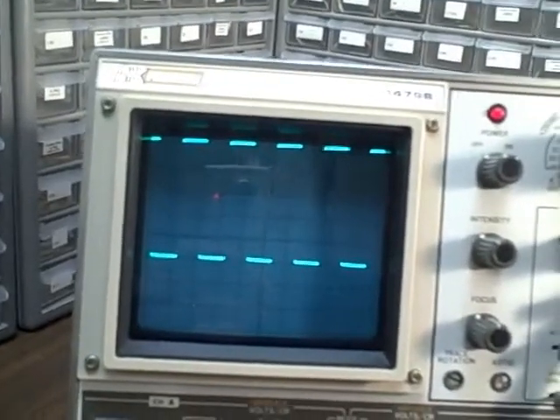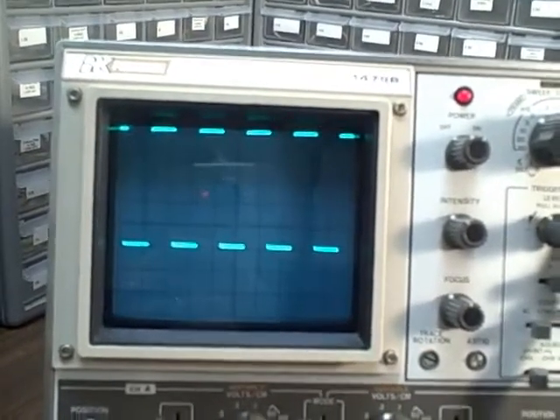Alright, so now I go to the ×10 setting on the probe, and I see that I am at a half a division, which would be 0.05 volts times 10 would be 0.5. 50 millivolts per division, coming up 1 full division, so 50 millivolts times 10 is 0.5. 20 millivolts per division, and we have 2 1/2 divisions, so 0.5. And 10 millivolts per division, we rise 5 divisions. So once again, channel B mimics channel A, and the inputs are all measuring properly vertically.